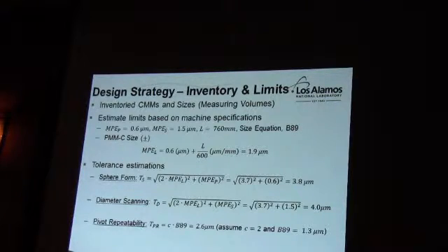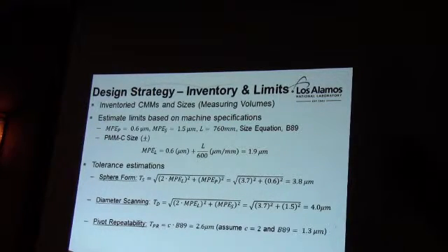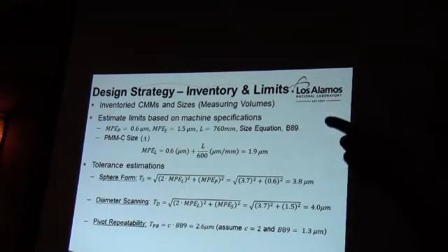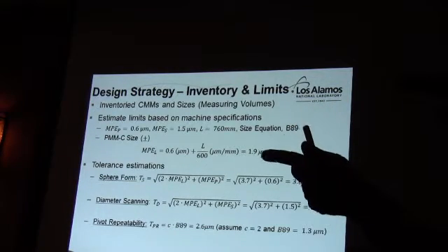We have a PMMC. This is a type of CMM by one of the manufacturers that is a moving table CMM. I won't get into too much detail, but the head is rigid, so we basically get rid of dynamic errors on the head from an articulation. These are some of the manufacturer specifications given to us. This MPE is a maximum permissible error. In other words, this is the maximum error for this particular test. P, we're calling probing. S, we're calling scanning. L is our length, basically the radius of our machine checking gauge.